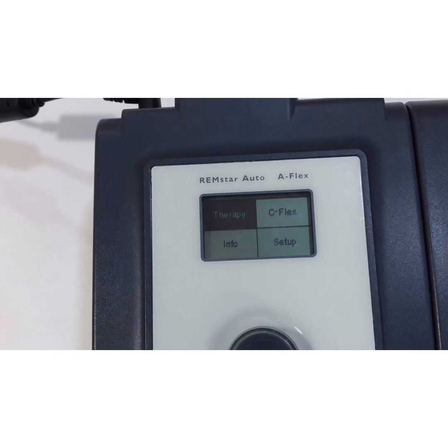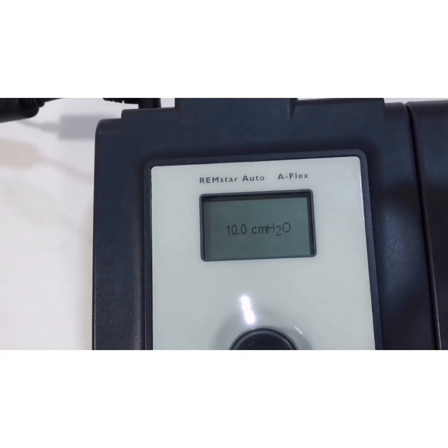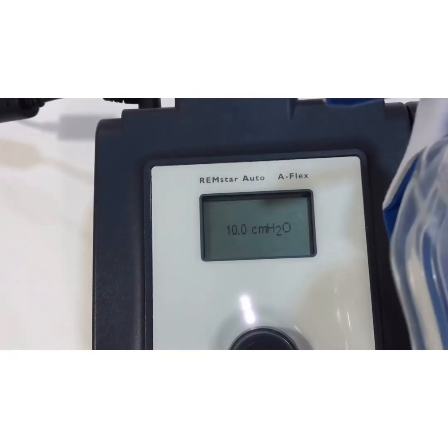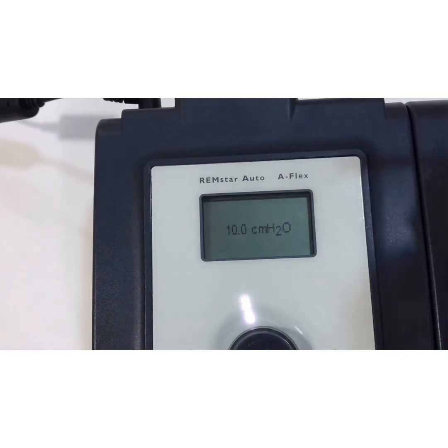What else can we explain? We explain one of the features: once there is, for example, a disconnection, the machine will give you an alarm. So as you see now, there is a disconnection. Let's say it is intentional. For example, the patient wanted to go to the bathroom and did not turn off the machine. So after almost 1 minute, the machine will start the alarm. So let's wait for it.